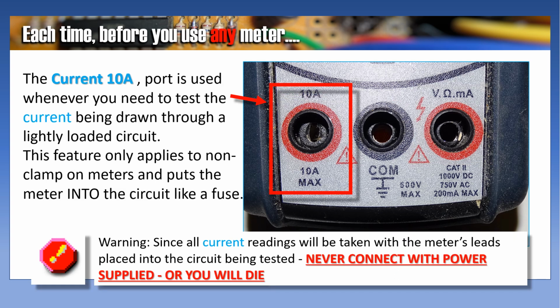The current 10 amp port is used whenever you need to test the current being drawn through a lightly loaded circuit. This feature only applies to non-clamp-on meters and puts the meter into the circuit like a fuse. Careful warning here. Since all the current readings will be taken with this meter and has the meter leads placed into the circuit being tested, never connect with power supplied, or you'll die. Simple as that.